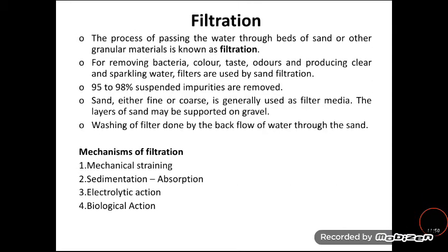Next one is the filtration process. This is the process in which water is allowed to pass through a bed of fine and coarse aggregate, that is, granular material, which is called filtration. It removes bacteria, color, odor and taste present in the water. In this process, about 95 to 98% of the suspended solids are removed.